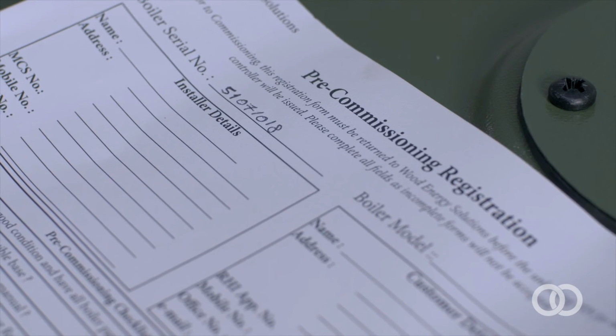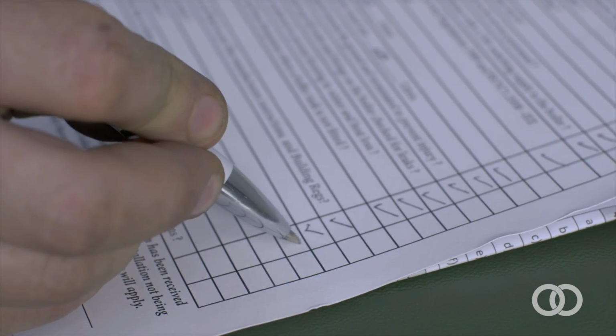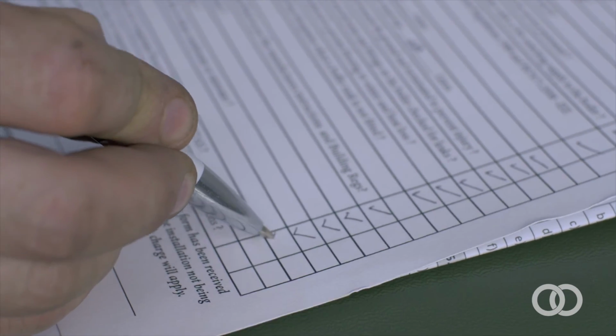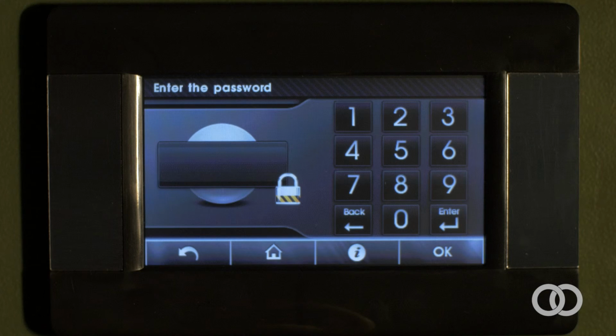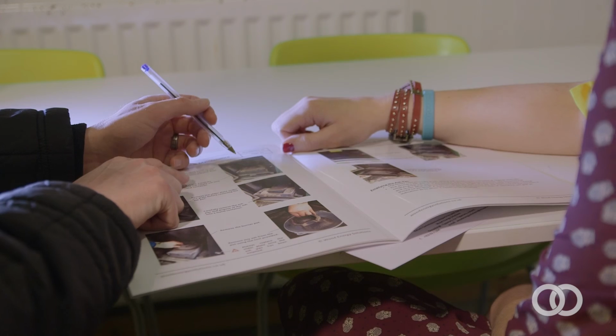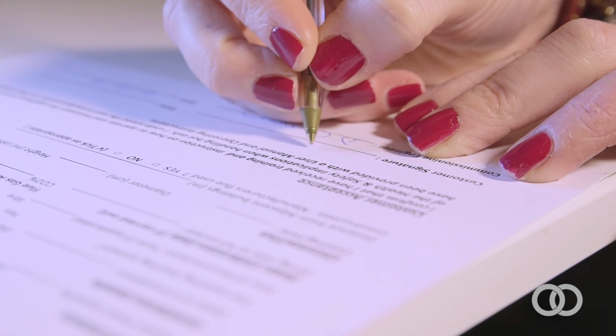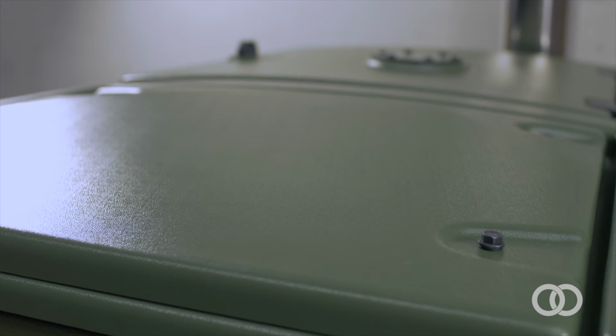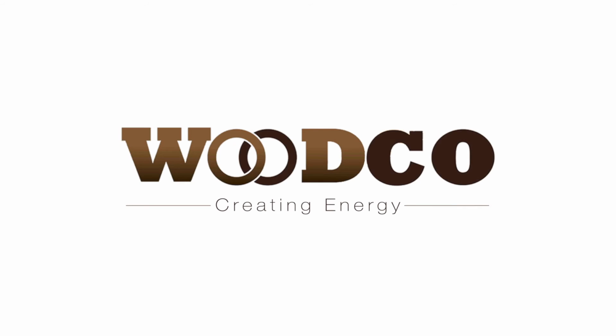Once the installer has primary plumbing connections completed and the boiler is ready for commissioning, a pre-commissioning registration form must be completed and returned to WoodCo. WoodCo will check that the form is complete and that the installation is ready for commissioning. Once WoodCo is satisfied, they will issue an unlocked PIN code to the commissioning engineer. Once the boiler has been commissioned, a 30 minutes handover to the homeowner must be done, and the homeowner will sign to confirm that they have received and understand the instructions on how to operate their boiler.